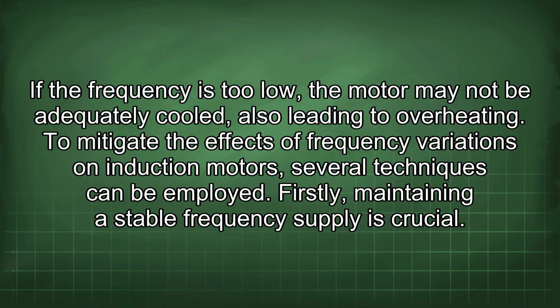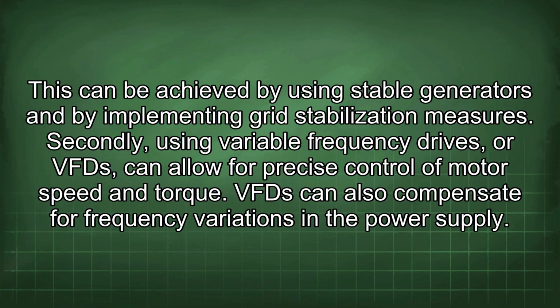To mitigate the effects of frequency variations on induction motors, several techniques can be employed. Firstly, maintaining a stable frequency supply is crucial. This can be achieved by using stable generators and by implementing grid stabilization measures. Secondly, using variable frequency drives, or VFDs, can allow for precise control of motor speed and torque. VFDs can also compensate for frequency variations in the power supply.